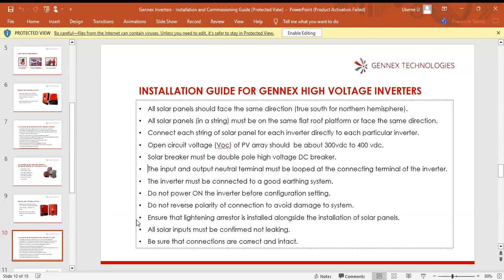All solar inputs must be confirmed. You have to carry out a solar test to be sure that there's no leakage. If there's leakage, the inverter can start misbehaving and it can even damage the MPPT or other components inside the inverter. So be sure there's no leakage between earth and any terminal, either positive or negative, of the inverter. Be sure that connections are correct.